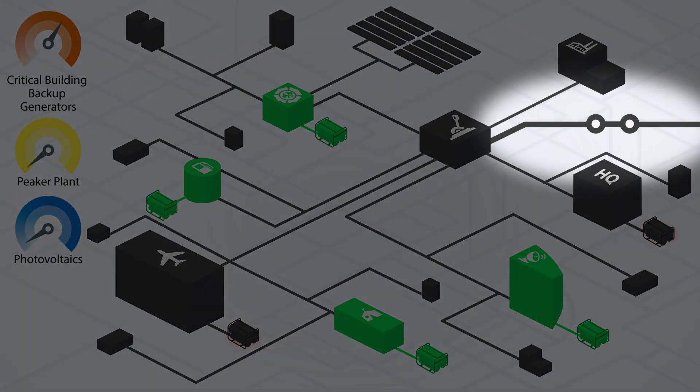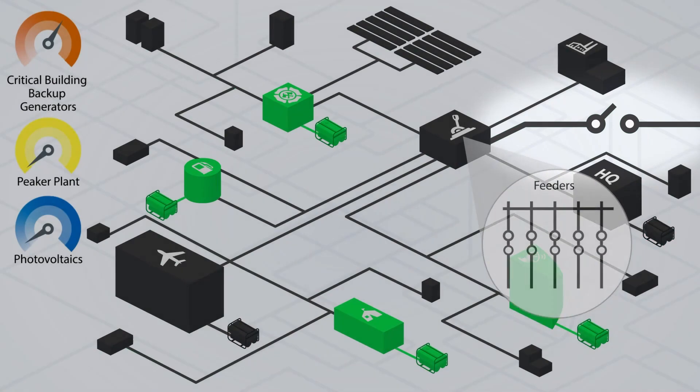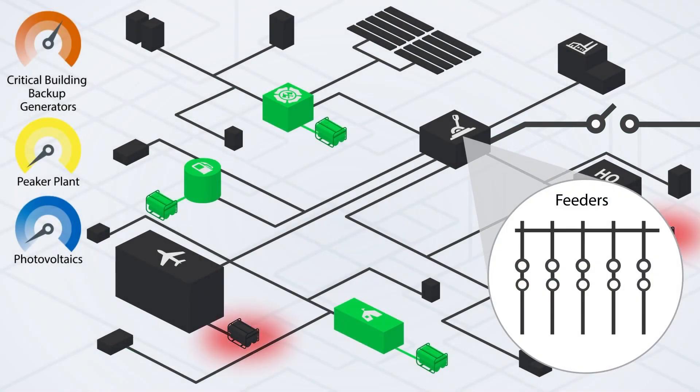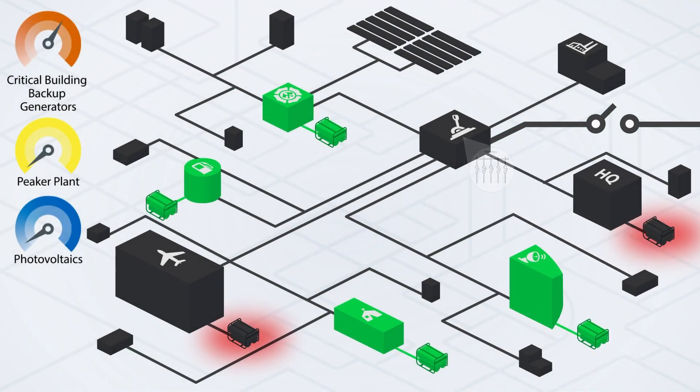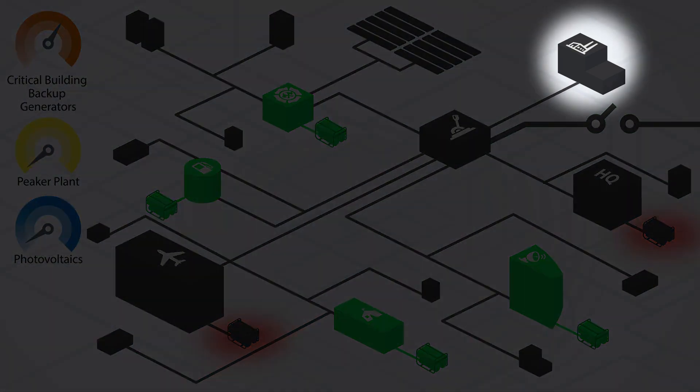To prepare for islanding, the main electric service disconnect opens. This is done to prevent back feeding electricity to the utility grid for safety reasons. At the main substation, all feeder breakers open. The peaker plant starts energizing the main substation.